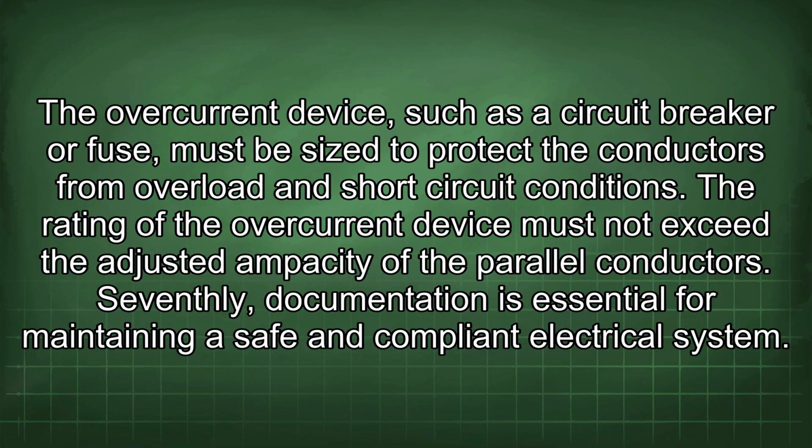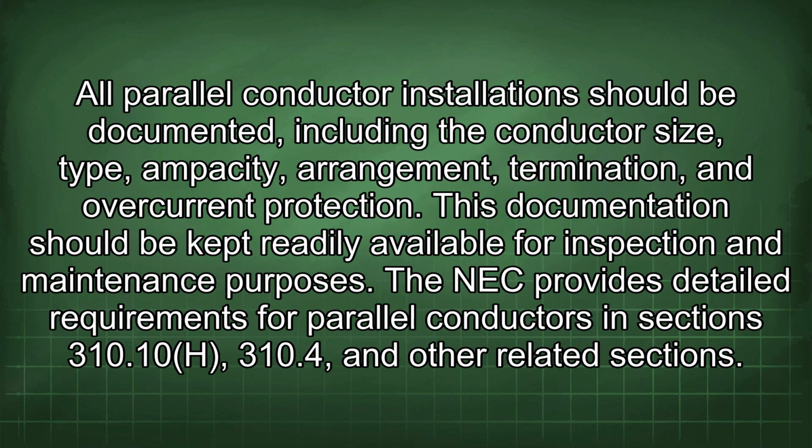The rating of the overcurrent device must not exceed the adjusted ampacity of the parallel conductors. Seventhly, documentation is essential for maintaining a safe and compliant electrical system. All parallel conductor installations should be documented, including the conductor size, type, ampacity, arrangement, termination, and overcurrent protection. This documentation should be kept readily available for inspection and maintenance purposes.